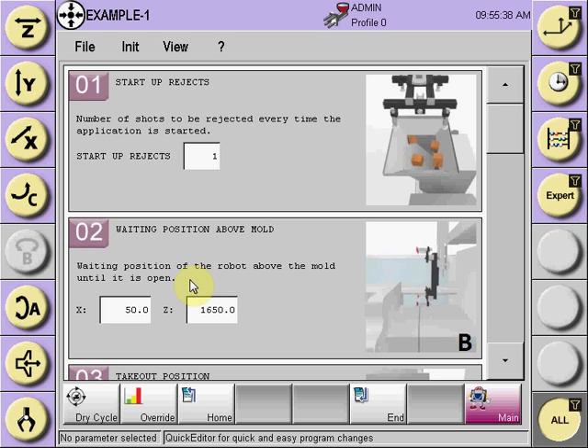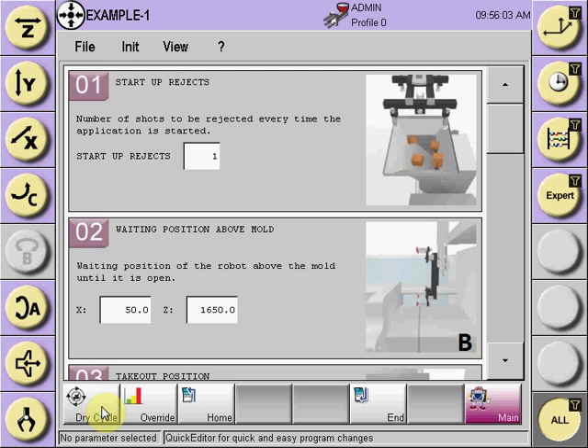To dry cycle the Quick Edit program, the robot must be in the reference position to begin, and the molding machine must be in manual with the mold open to its open position. On the lower left-hand side, once the robot has been put in the reference position, the dry cycle button will illuminate.